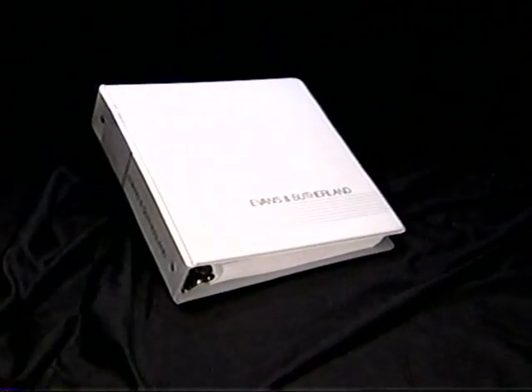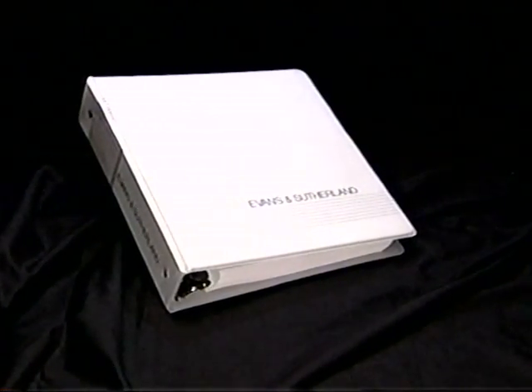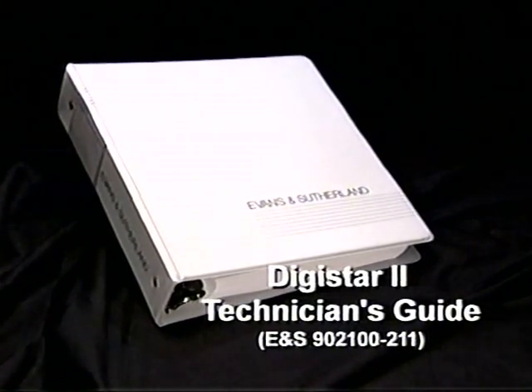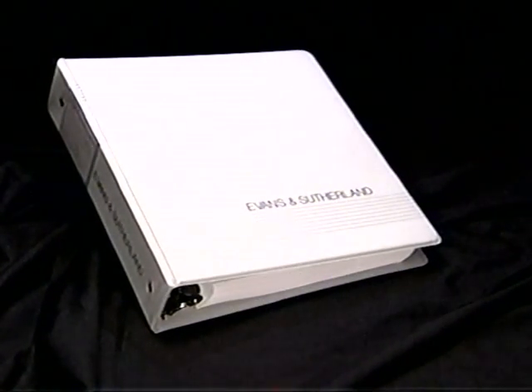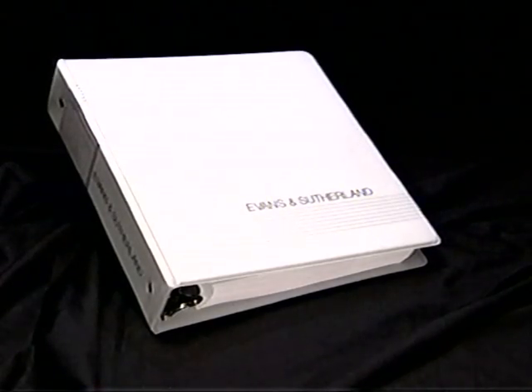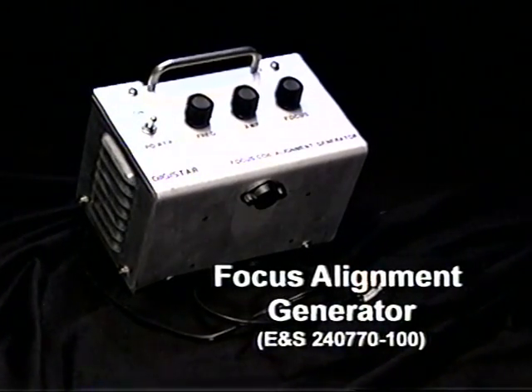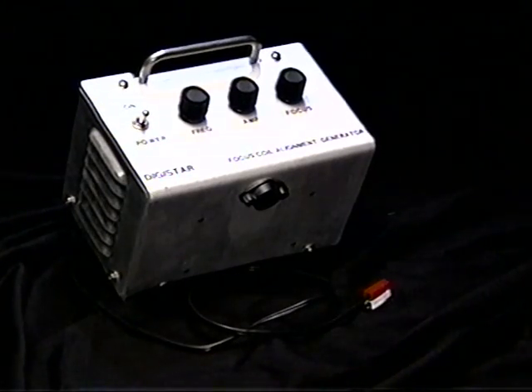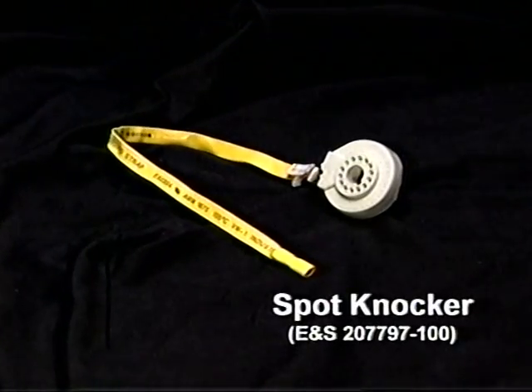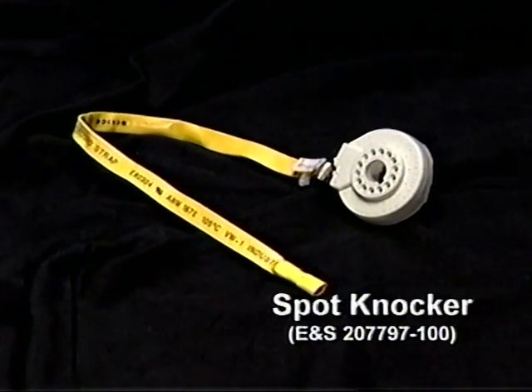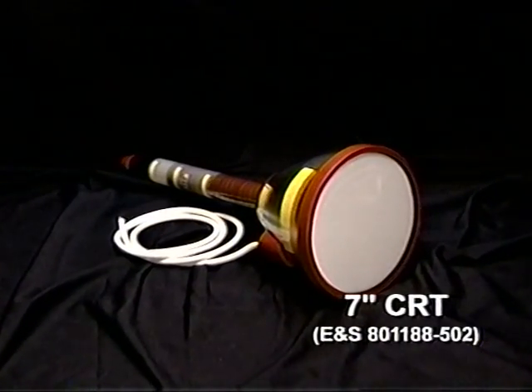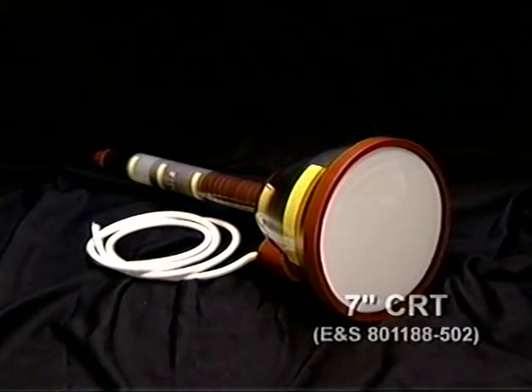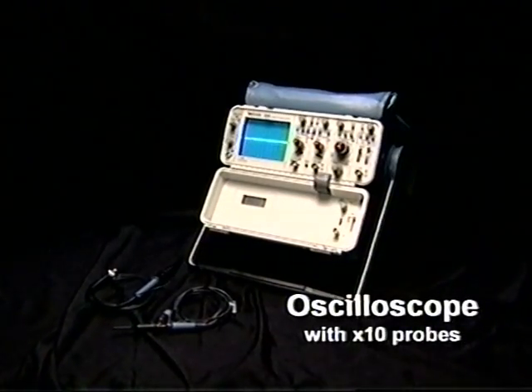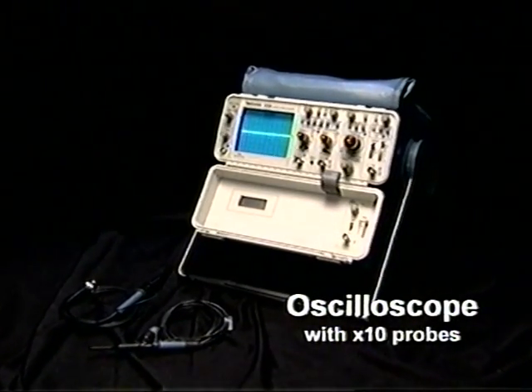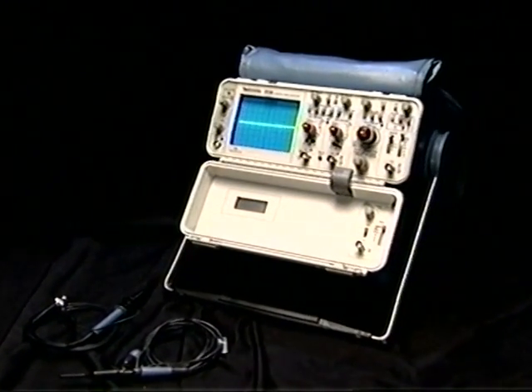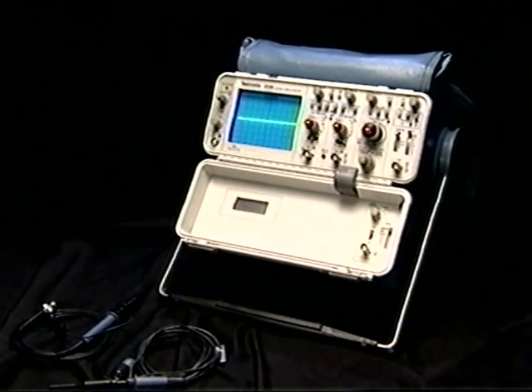Before we begin, here is a list of tools and parts you will need to replace your CRT. Digistar II Technician's Guide, Revision C or later. This is also available online from the D2 workstation. Focus Alignment Generator, commonly referred to as a jitter box. One of these was shipped with your system. Spot Knocker. One of these was shipped with your system as well. New CRT, or a refurbished CRT from MII. Oscilloscope with ×10 probes. The oscilloscope should have a minimum bandwidth of 60 MHz. 2 probes are recommended, although only 1 is required.